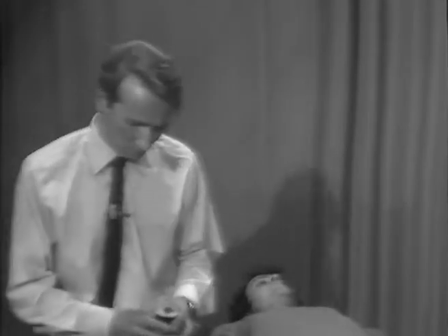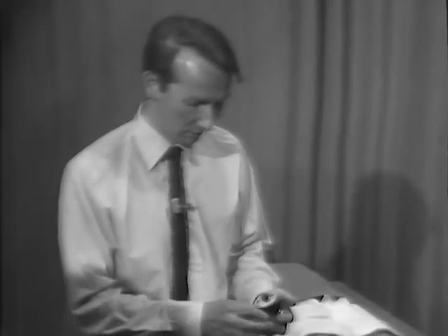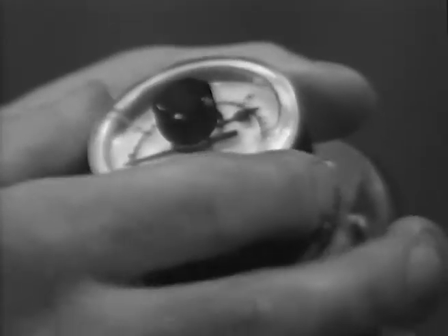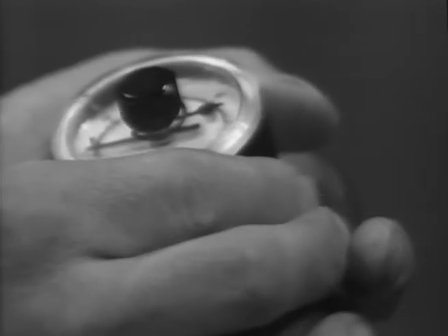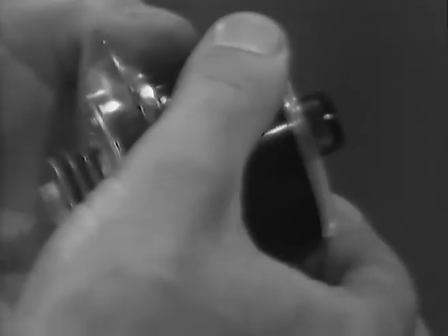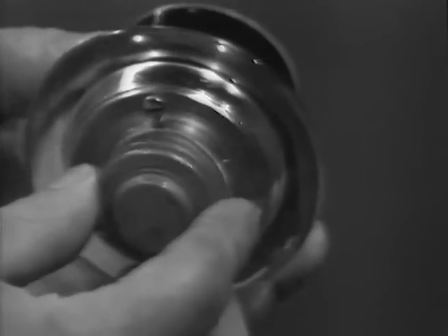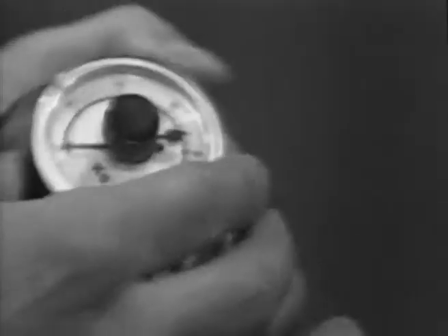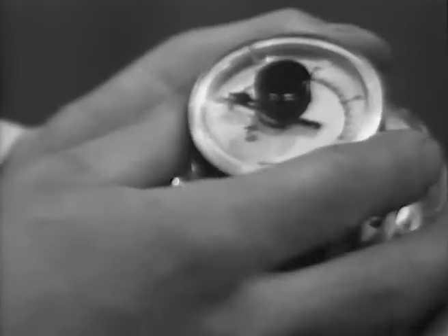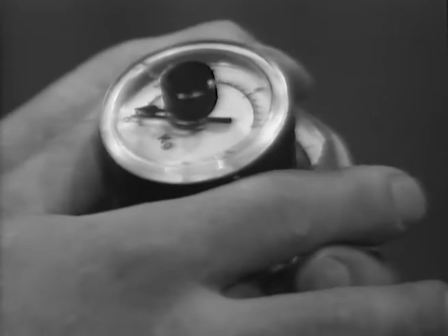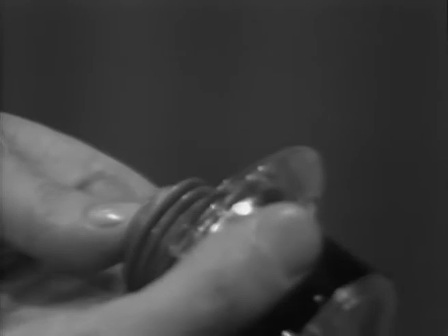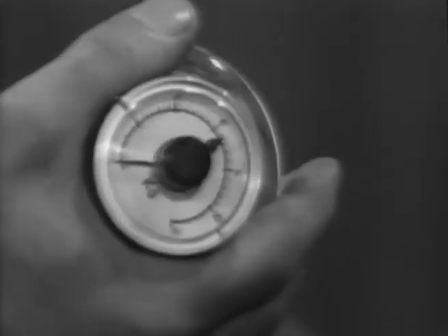This little instrument here is a clinical force dynamometer which we recently developed for use at Hammersmith on our patients complaining of muscle weakness and fatigue. You'll see here that it comprises a metal bellows. This is oil filled and it's connected to a pressure gauge, and then with this little dial on the upper surface of it, it's possible to see the maximum force that is generated in contact between the examiner's hand and the part of the body to which it is being applied.